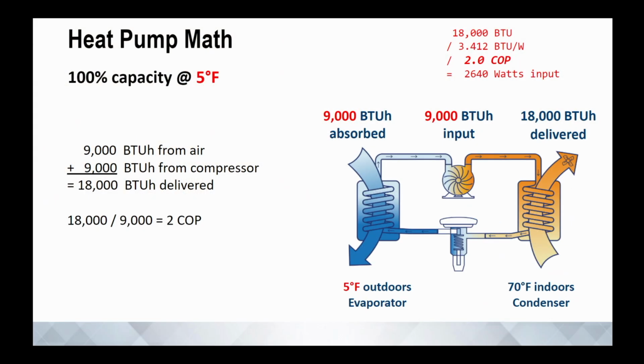And ask questions, please. So what we have here is the refrigerant cycle. We've got 9,000 BTUs. We're getting towards 18,000 BTUs. Arbitrary 1.5 ton size, don't worry about that. Just know that we're targeting 18,000 BTUs, and we're operating at about 200% efficient. So there's 9,000 BTUs absorbed from the air outside, and we're investing 9,000 BTUs in the compressor. That's what we're paying for on our utility bill or from our solar panels or from our batteries or what have you. So we've got this 1-to-1 ratio to create 18,000 BTUs of heat.